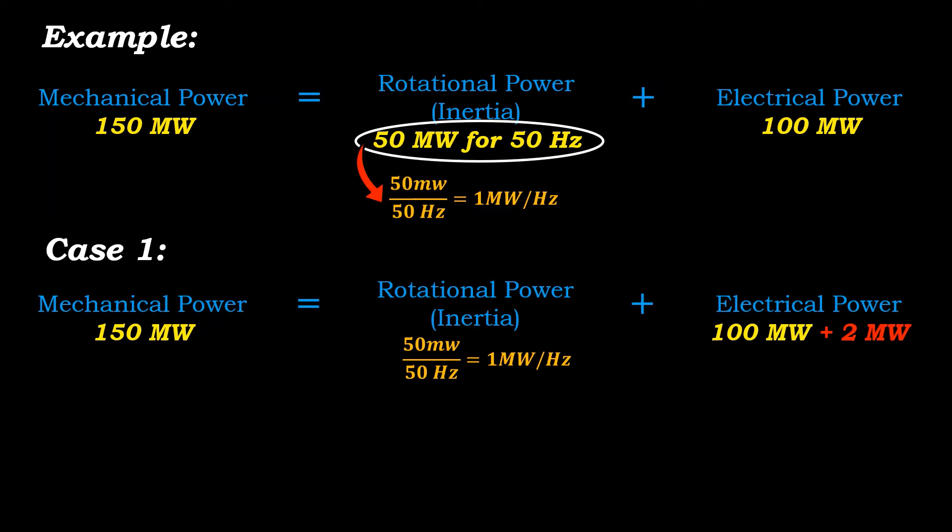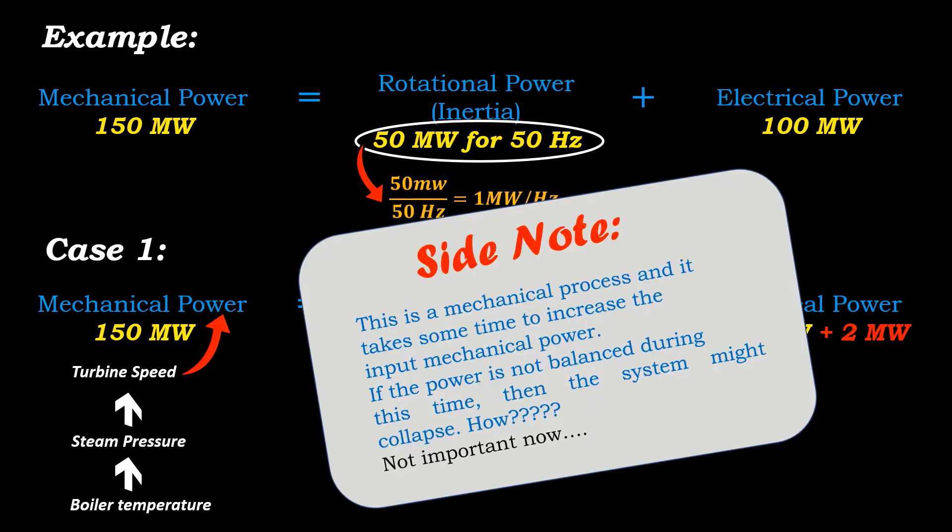However, increasing the mechanical input power is a time-taking process and cannot be done instantaneously. For that, initially we increase boiler temperature, this increases steam pressure which increases turbine speed and eventually input rotor mechanical power increases. During this whole process, if power is not balanced then it might collapse the system.